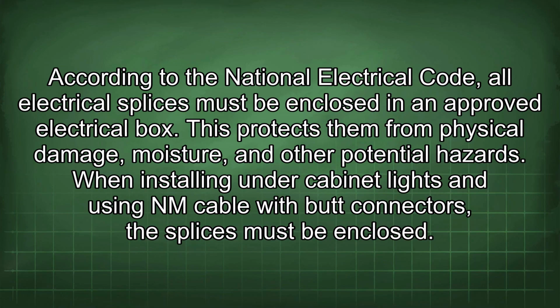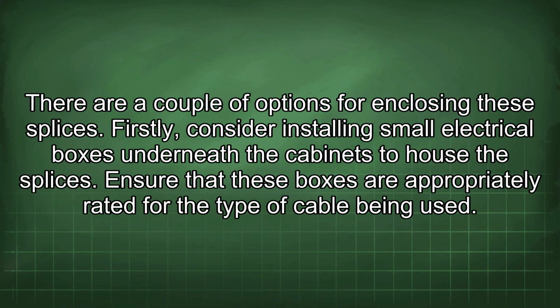According to the National Electrical Code, all electrical splices must be enclosed in an approved electrical box. This protects them from physical damage, moisture, and other potential hazards. When installing under-cabinet lights and using an NM cable with butt connectors, the splices must be enclosed. There are a couple of options for enclosing these splices.